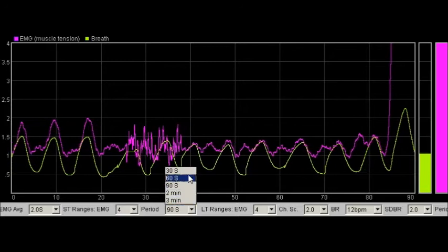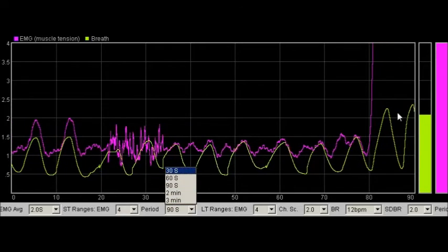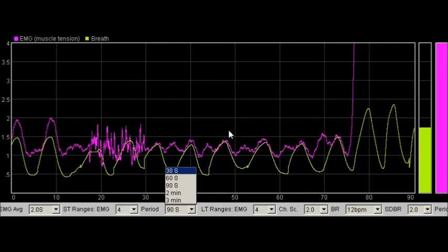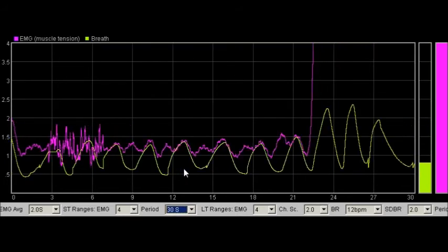The third control sets the length of time it takes for the traces to traverse the whole chart from right to left, or in other words the horizontal range. You can see that if I set it to something lower, the traces go faster.